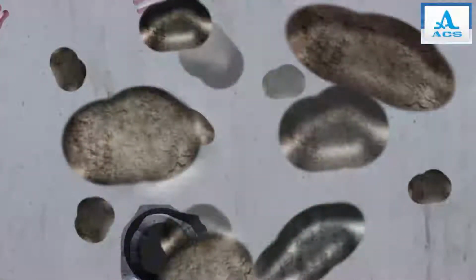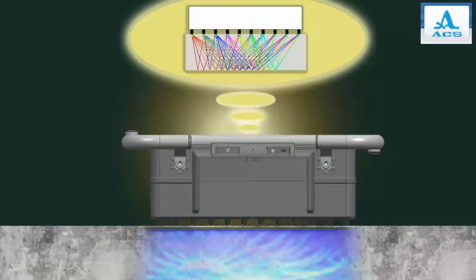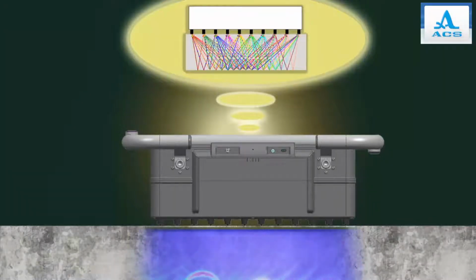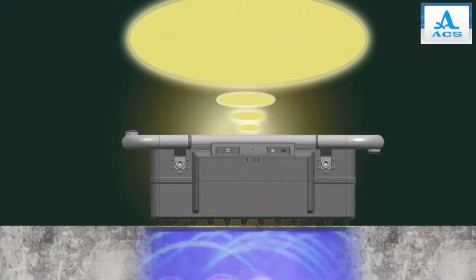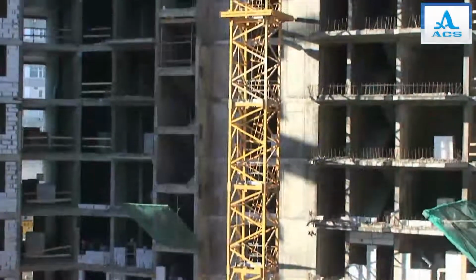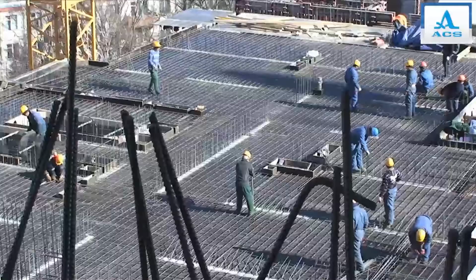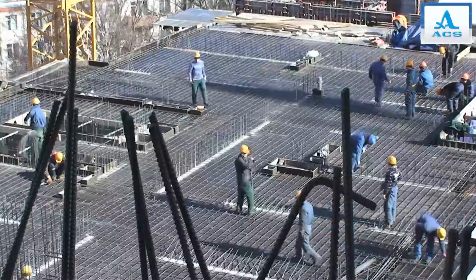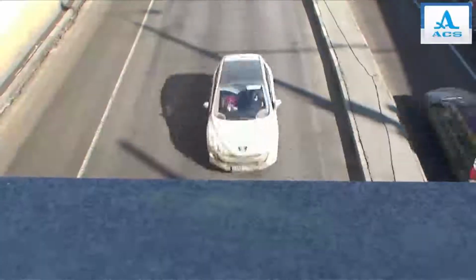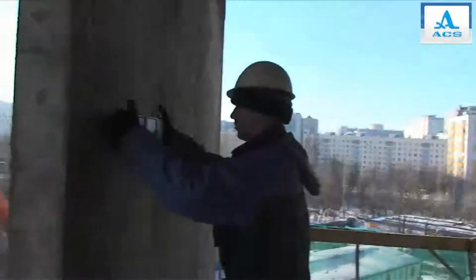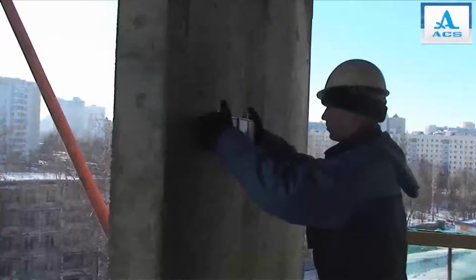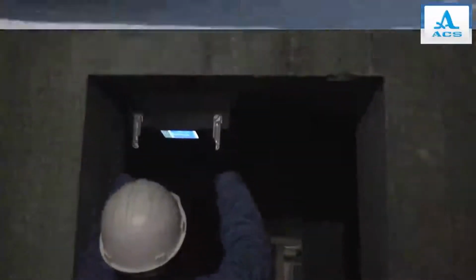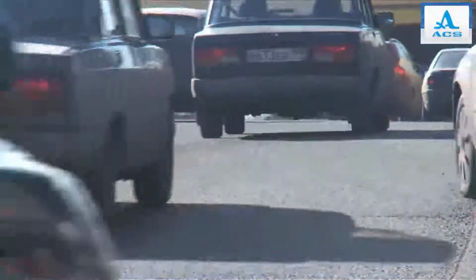During the time of a double pass through the concrete structure, the ultrasonic wave partly scatters and gets absorbed, but the echo signal fixed not by one, but by 48 highly sensitive elements visibly stands out against the background of occasional re-reflections. The MIRA instrument can be used as a one-sided test method to investigate problems in high-rise building facades, tunnels and underpasses, highway pavements, bridge decks, etc.